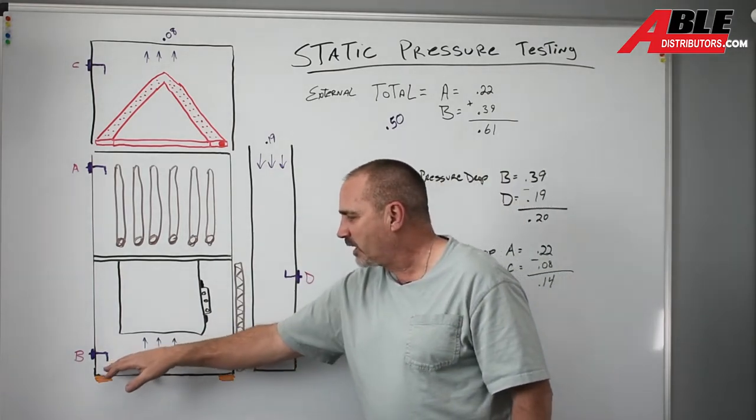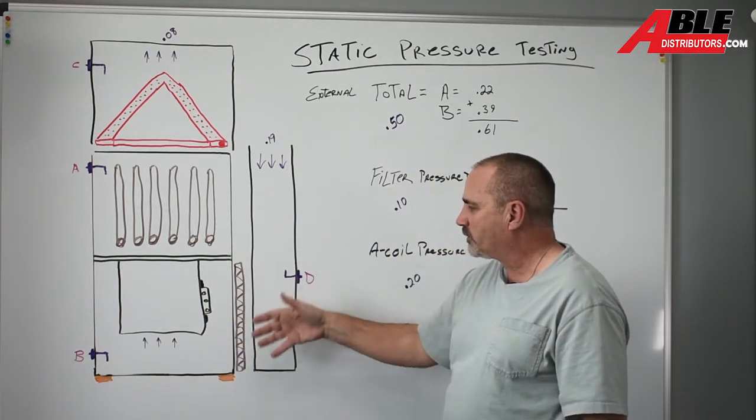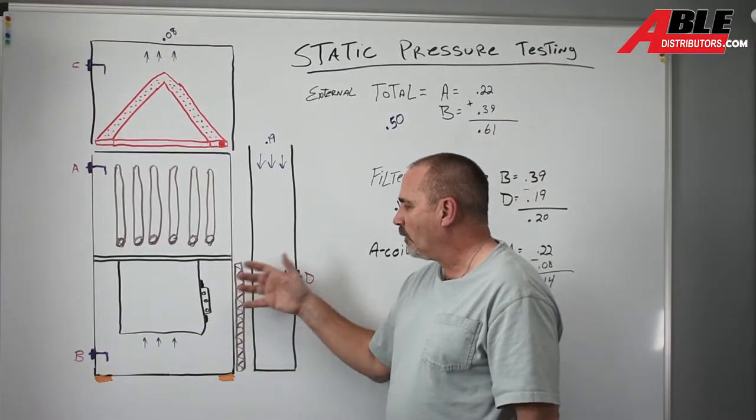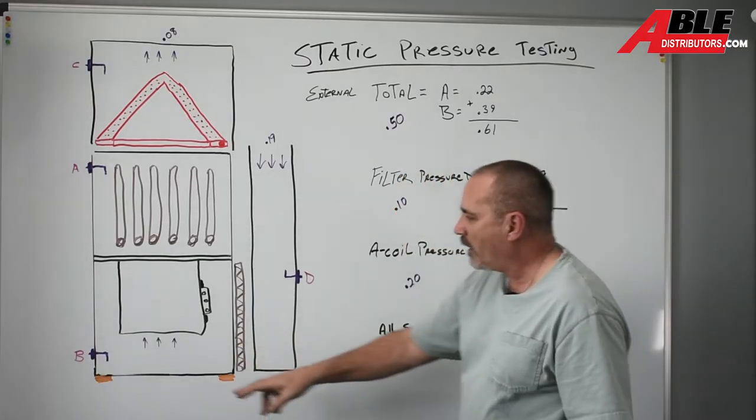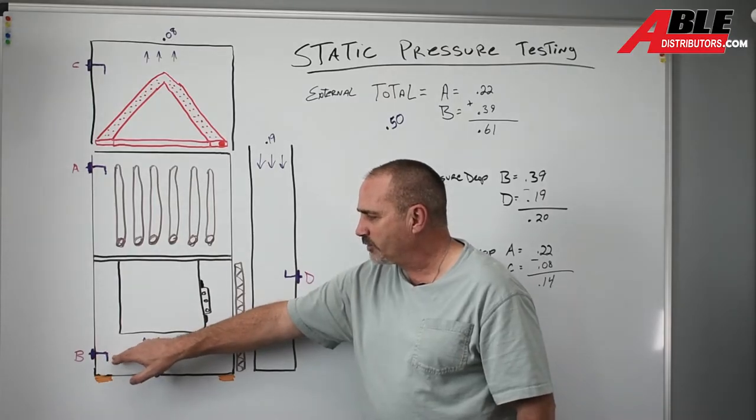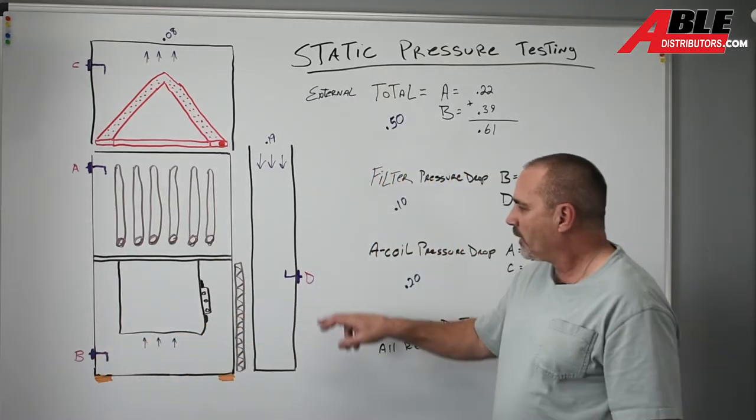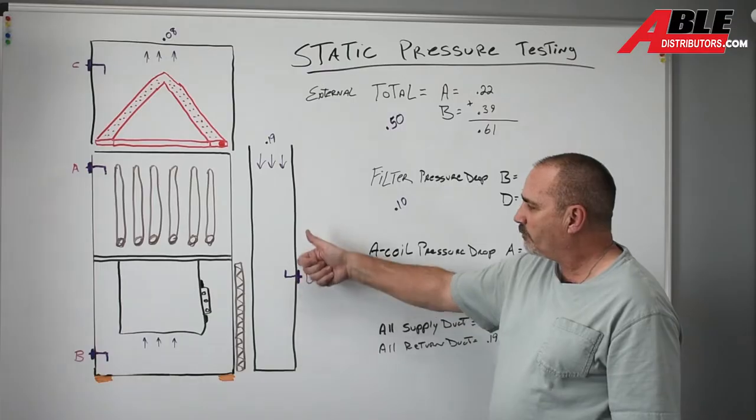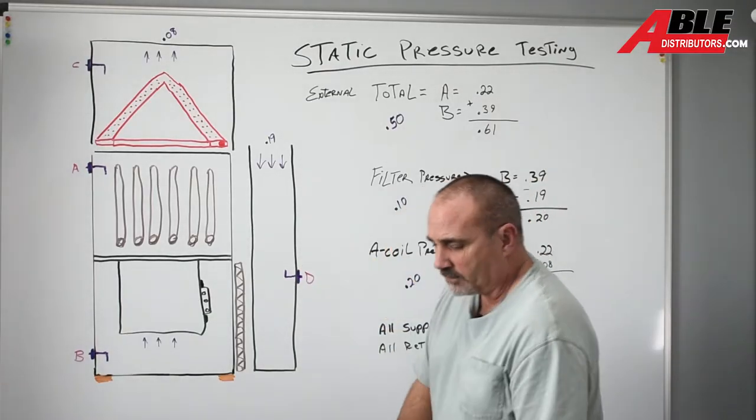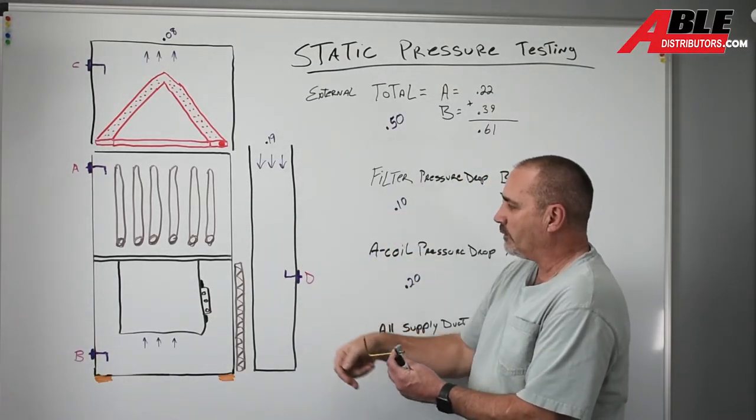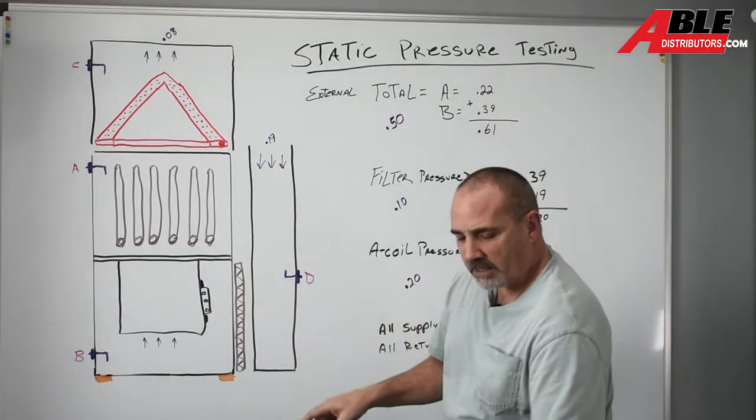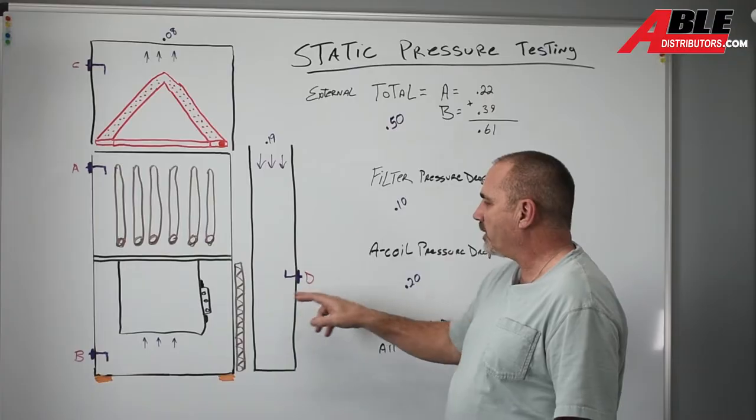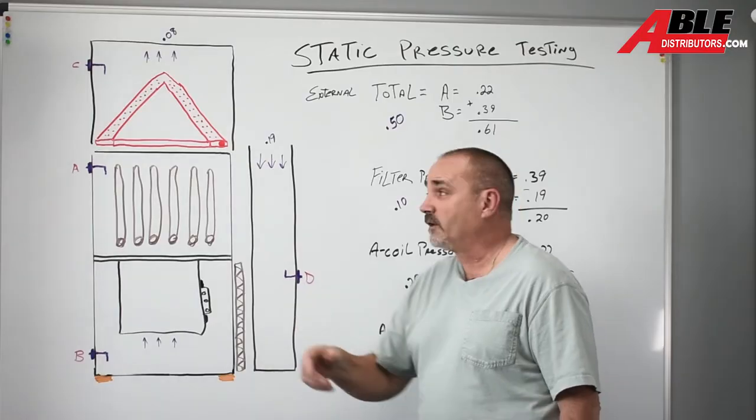So the next step is to check the filter, how much restriction, how much are we losing going across that filter. So now we leave one probe in position B in the blower compartment, and we're going to put another one with the probe facing up since the return air comes down. And we're going to take B subtract D and that's going to tell us how much we're losing across that filter.